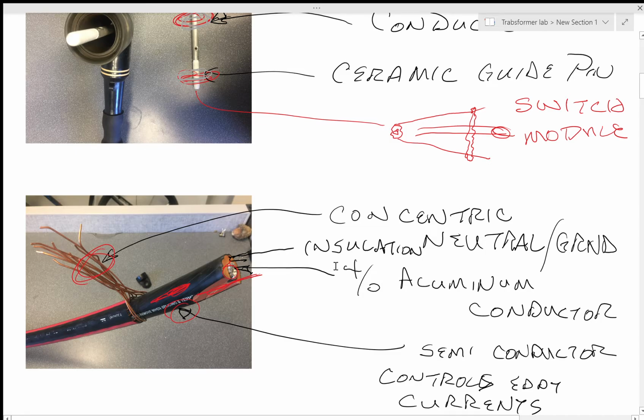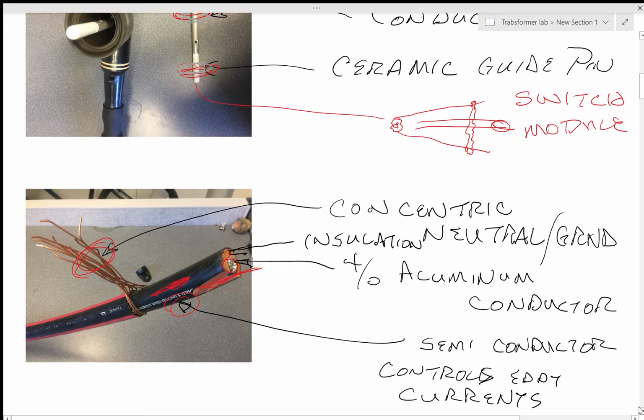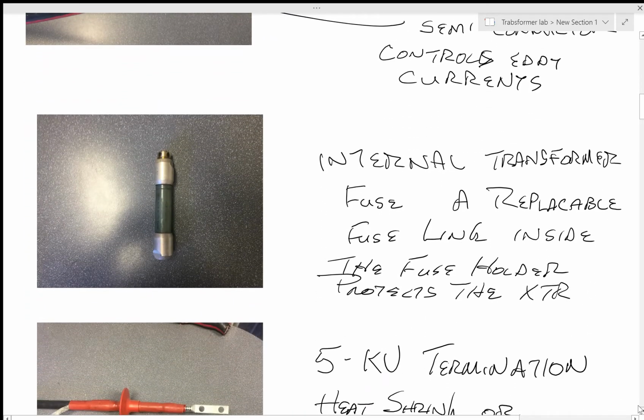So that's an elbow and what it's terminated on, that type of stuff. Also, in a transformer, you have two different types of fuses. This is an internal fuse link. Basically, you just take this thing apart, stick a fuse link in there, put the ends back on, and stick it back into the tub and its little mounts in the tub of oil. So if it blows a fuse, you can easily just go in there, turn it off, pull that link out, pull it open, put a new link in, close it back up, and stick it back in the oil, and it's insulated and it works. So it's like a fuse.